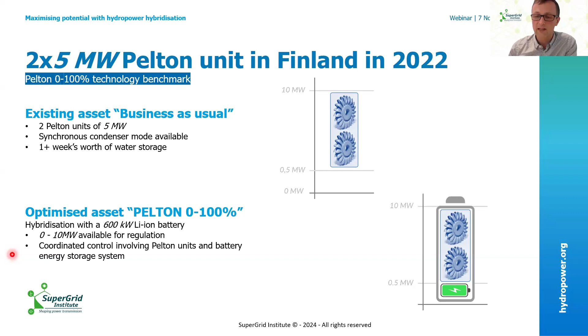So from the synchronous condenser mode to 10 megawatts. That's basically like behaving like a big battery of 10 megawatts, and this is done through the coordinated control of the Pelton and the lithium-ion battery.